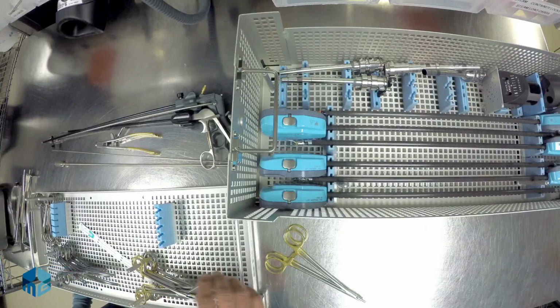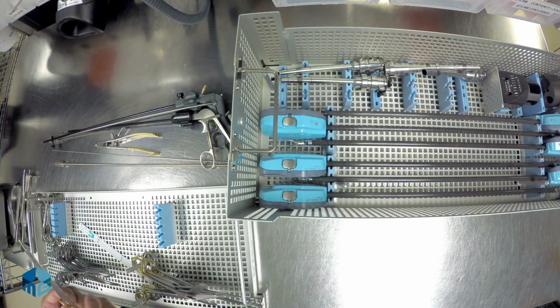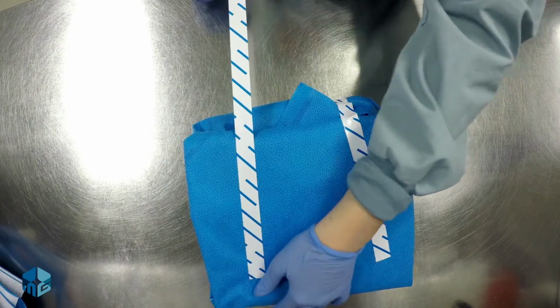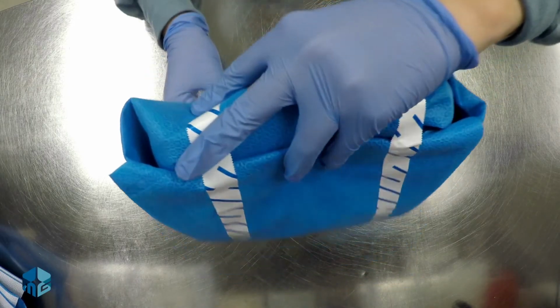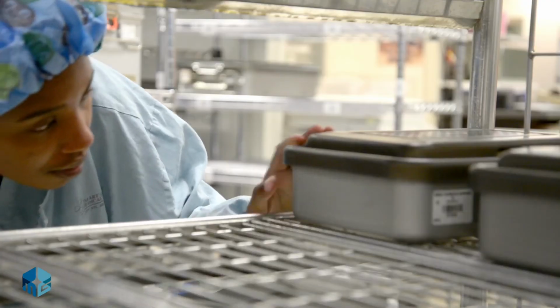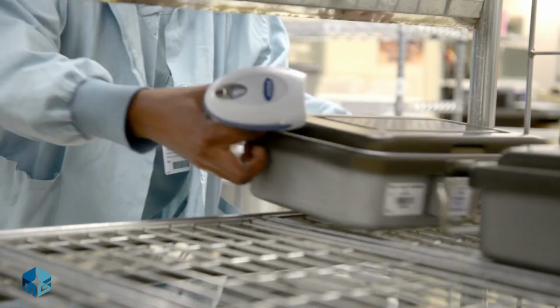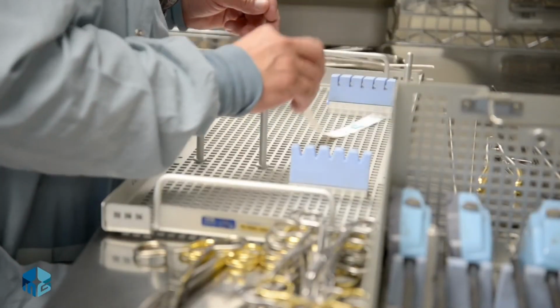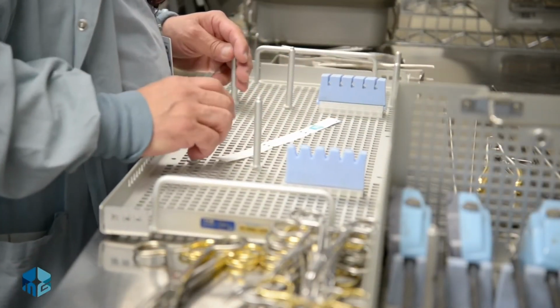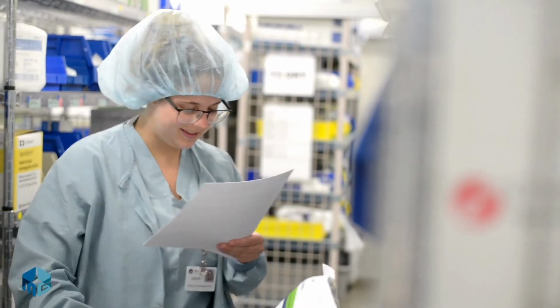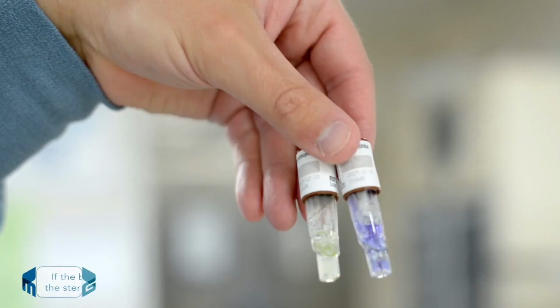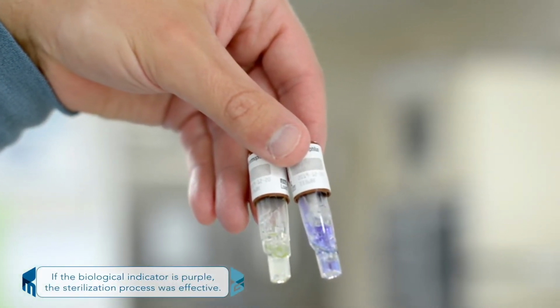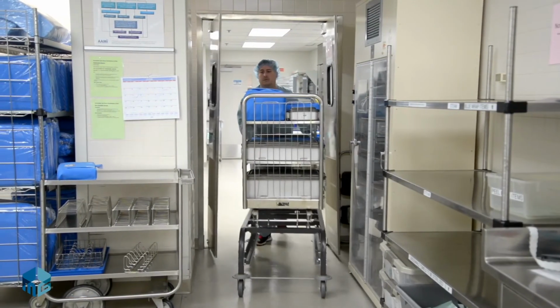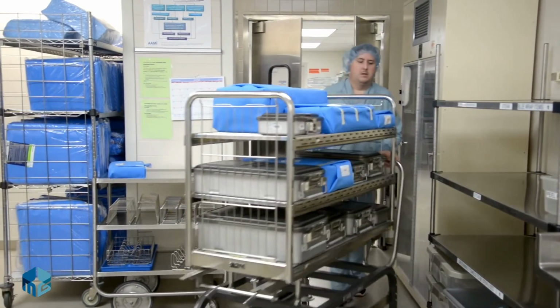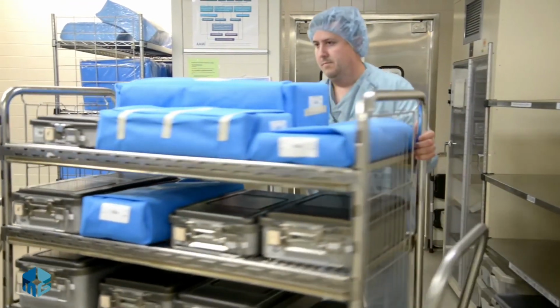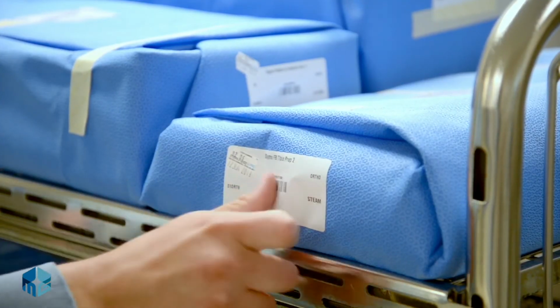To make sure the sterilization process has been effective, we use chemical and biological indicators. Chemical indicators are placed on the outside of blue wrap or a rigid container and allow us to know at a glance that the instruments have gone through the sterilization process. They are also placed inside the container with the instruments so the surgical staff knows the instruments were sterilized and safe for use on our patients. The biological indicators help us verify that our sterilization process is effective enough to kill all the germs that may be on our instruments. This process helps us know we can provide patients with the best possible care.